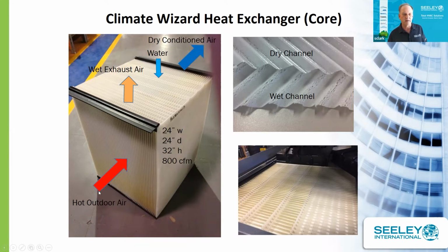Of conditioned air coming out. So we have the hot outdoor air coming in through, and this air goes through the dry sheets. And then we have water in this section that goes through the wet sheets. And then we have our exhaust air coming up here through the heat exchanger that's exhausted to atmosphere. These modules are made in Australia, and then we put those in our units that are made here in Denver, as well as Australia puts the units in the CW80 units that are made over there.